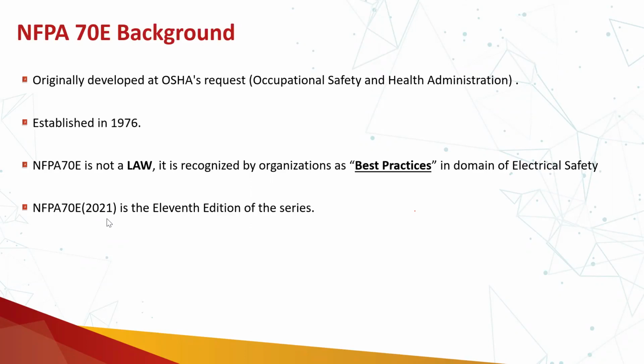Zishan is asking whether the shall statements in 70E are backing OSHA requirements. No, they are not backing OSHA requirements. It means that if you want to apply 70E in your organization and get certified against it, you have to implement all the shall requirements stated in NFPA 70E.